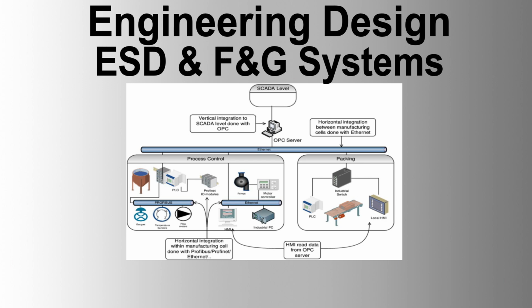2. Manufacturing and supply. Provision of fully engineered and assembled system cabinets, marshalling cabinets, and related hardware. Supply of dual redundant processors, I/O modules, power supplies, and communication equipment. Hardware and software necessary for system operation and integration. 3. Installation and integration. Installation of ESD F&G equipment in specified local equipment rooms. Integration with existing control systems and ensuring compatibility. Implementation of required upgrades to firmware or software for seamless integration.